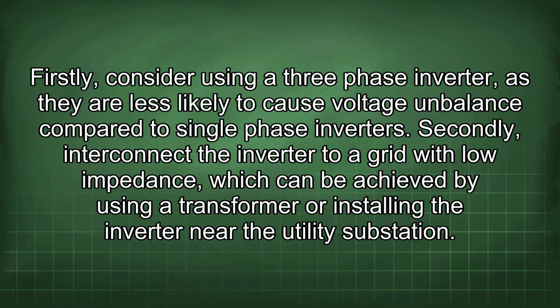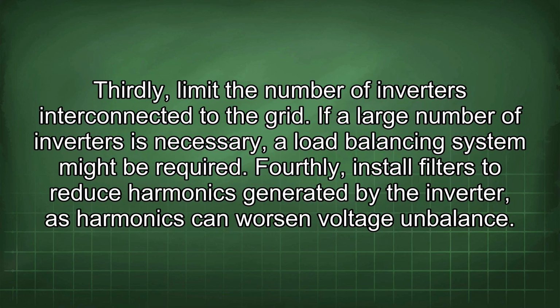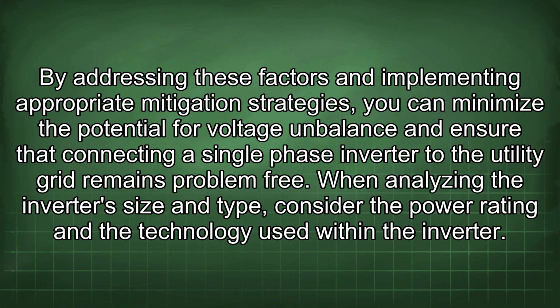Firstly, consider using a three-phase inverter, as they are less likely to cause voltage imbalance compared to single-phase inverters. Secondly, interconnect the inverter to a grid with low impedance, which can be achieved by using a transformer or installing the inverter near the utility substation. Thirdly, limit the number of inverters interconnected to the grid. If a large number of inverters is necessary, a load balancing system might be required. Fourthly, install filters to reduce harmonics generated by the inverter, as harmonics can worsen voltage imbalance. By addressing these factors and implementing appropriate mitigation strategies, you can minimize the potential for voltage imbalance and ensure that connecting a single-phase inverter to the utility grid remains problem-free.